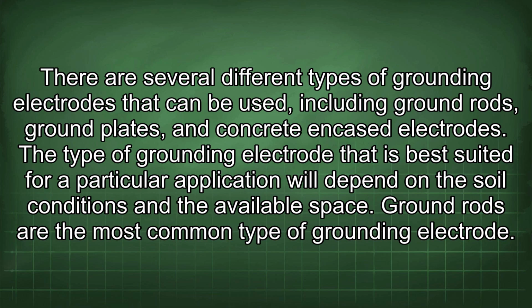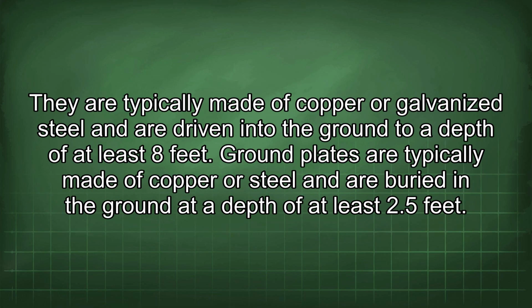Ground rods are the most common type of grounding electrode. They are typically made of copper or galvanized steel and are driven into the ground to a depth of at least 8 feet. Ground plates are typically made of copper or steel and are buried in the ground at a depth of at least 2.5 feet.